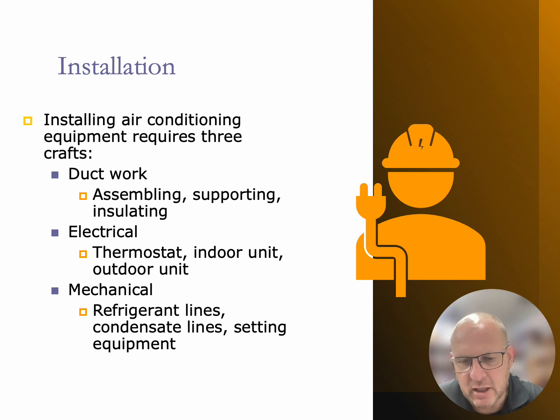And then mechanically, you have to be able to braze. And I know there's a lot of individuals out there who say, I don't have to braze anymore because we have this thing called Zoom lock. I'll tell you now that any person can push a button and seal up a refrigeration line. But when it comes to actually fixing a refrigeration coil or brazing systems that are properly done with purging of nitrogen and stuff, you cannot replace a technician that has that type of skill.